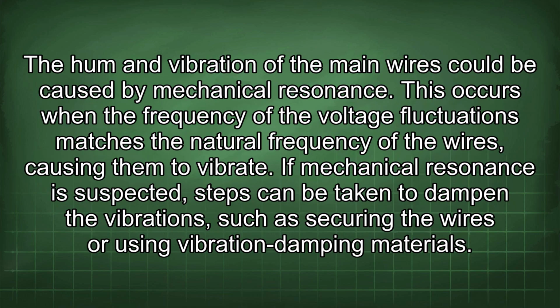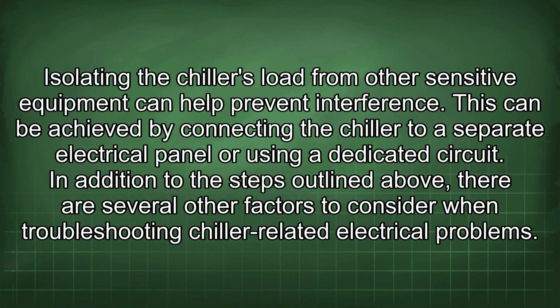The hum and vibration of the main wires could be caused by mechanical resonance. This occurs when the frequency of the voltage fluctuations matches the natural frequency of the wires, causing them to vibrate. If mechanical resonance is suspected, steps can be taken to dampen the vibrations, such as securing the wires or using vibration damping materials. Isolating the chiller's load from other sensitive equipment can help prevent interference. This can be achieved by connecting the chiller to a separate electrical panel or using a dedicated circuit.